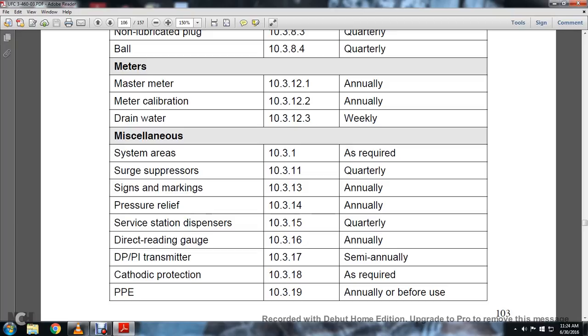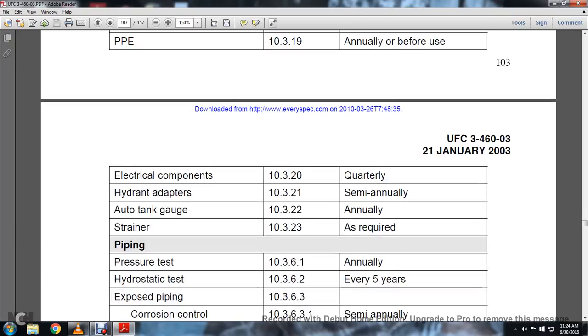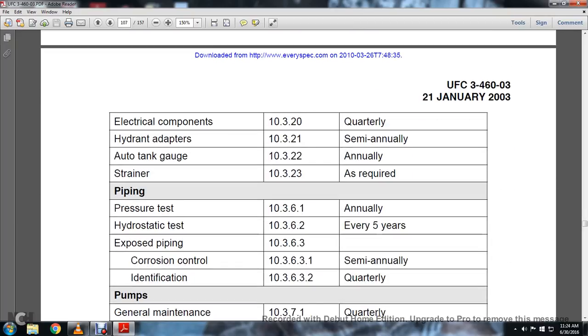PPE 10.3.19 annually or before use. Electrical components 10.3.20 quarterly. Hydrant adapters 10.3.21 semi-annually. Auto tank gauge 10.3.22 annually. Strainer 10.3.23 as required. Piping pressure test 10.3.6.1 annually. Hydrostatic test 10.3.62 every 5 years.